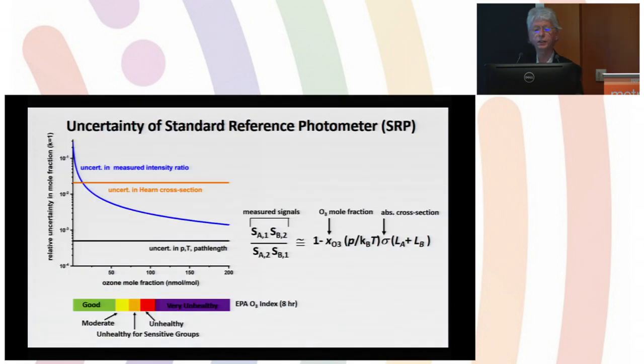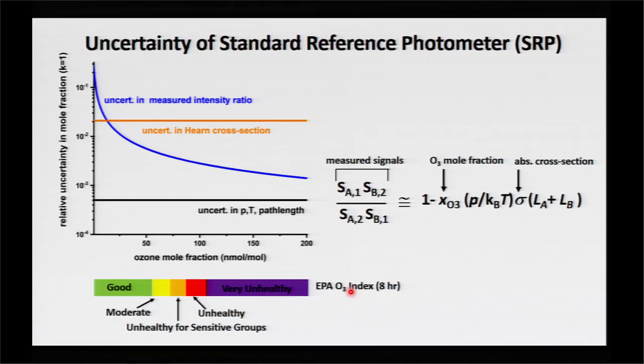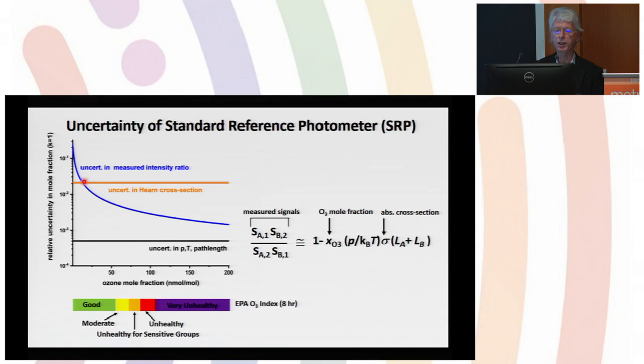The current SRP uncertainty budget looks like this. We have two dominant components: the type A component due to measurement of beam intensities, which is a function of ozone molar fraction. I'm showing also the relevant concentration scales for regulatory regulations and ozone human health issues. As soon as you get above about 13 parts per billion of ozone, the dominant uncertainty is the type B uncertainty associated with the Hearn cross section at about two percent.